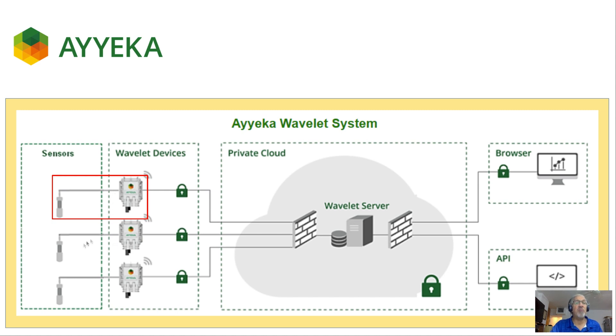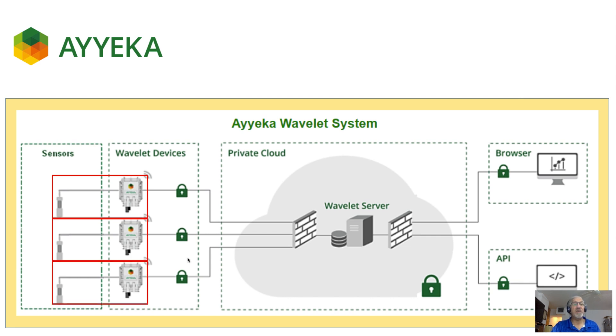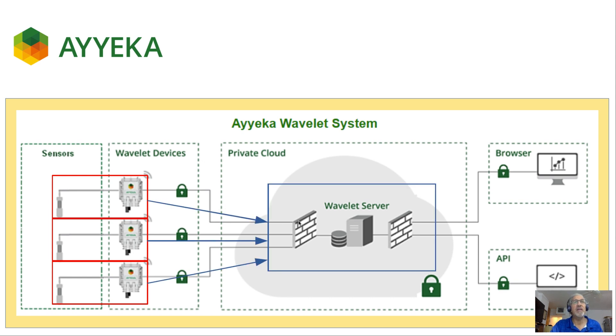The wavelet powers up the sensor at a user-defined frequency, which we refer to as the sampling rate, takes the data that is measured by the sensor, stores the data internally, and waits for the next transmission cycle for it to transfer the stored sensor data to the server. To do this, the wavelet powers up its internal cellular modem, attempts to connect to the best cellular network provider in the area, and then transmits the data to the server.